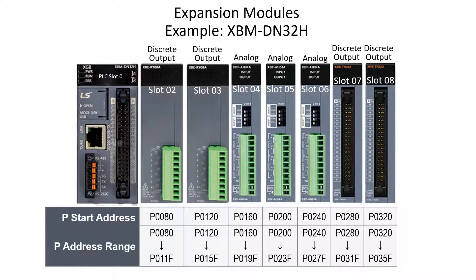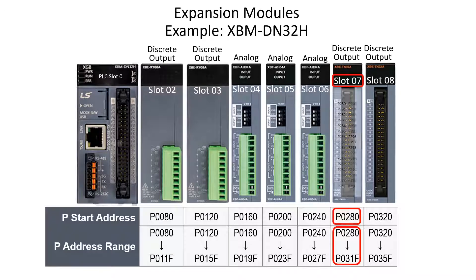A 32-point digital output module is configured in slot 7. The starting address is P-Word 28 bit 0 and the range is P28 0 through P31 F. The 32 output points are addressed P28 0 through P31 F.